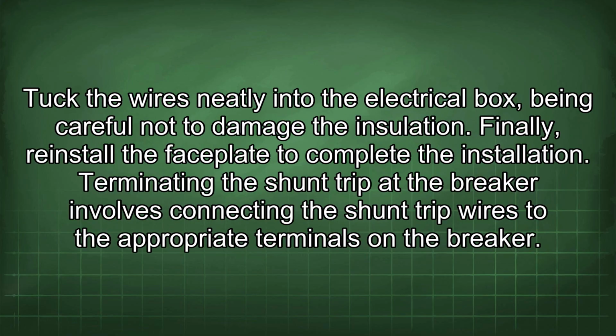Tuck the wires neatly into the electrical box, being careful not to damage the insulation. Finally, reinstall the faceplate to complete the installation. Terminating the shunt trip at the breaker involves connecting the shunt trip wires to the appropriate terminals on the breaker.